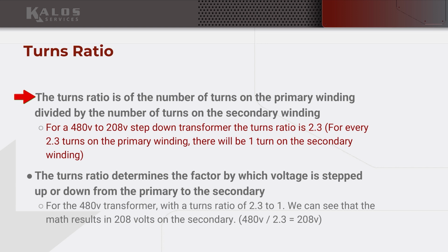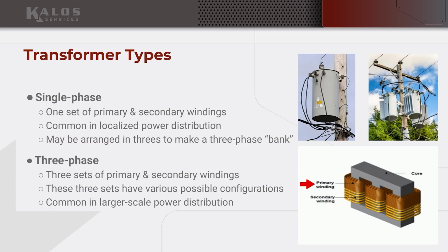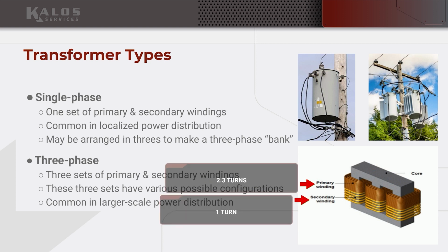The turns ratio is the number of turns on the primary winding divided by the number of turns on the secondary winding. For most transformers we see out there with a 480 volt primary, in fact all of them that go from 480 volt to 208 volt secondaries, will have a turns ratio of 2.3 to 1. That means on your 480 volt side, going back to this illustration, the primary coil will have 2.3 turns for every 1 turn on the secondary winding.